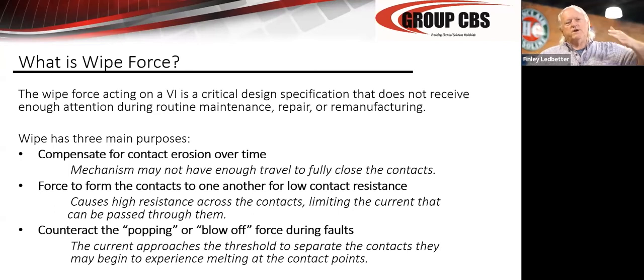But you get a wear spec that says, hey, when these contacts wear X amount, there's normally two pointers. And it says when this exceeds this, the breaker can be fairly new. The vacuum interrupter can still have a substantially good vacuum inside of it, and the contact resistance can still be good. But what's happened is you've exceeded the wear limit, which means the spring can no longer exert proper wipe spring force on the contacts. So it's very important you watch your wear limiters.